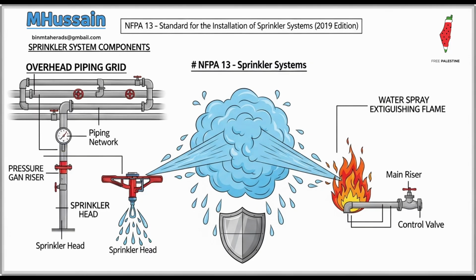But when you move up to the high temperature classification, say 250 degrees F to 300 degrees F, the frame arms are blue, and the liquid bulb is also blue. So if you walk into a standard office space and you see a blue sprinkler head, well, you know immediately that either that head is significantly oversized for the actual risk, or there's some unusually high heat source nearby that shouldn't be there.